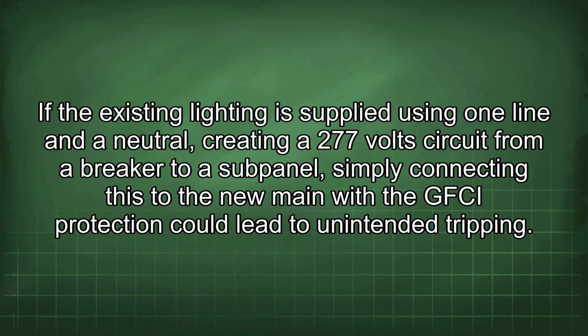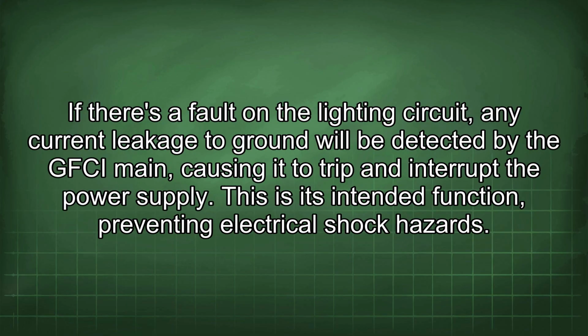from a breaker to a subpanel, simply connecting this to the new main with the GFCI protection could lead to unintended tripping. If there is a fault on the lighting circuit, any current leakage to ground will be detected by the GFCI main, causing it to trip and interrupt the power supply. This is its intended function, preventing electrical shock hazards.